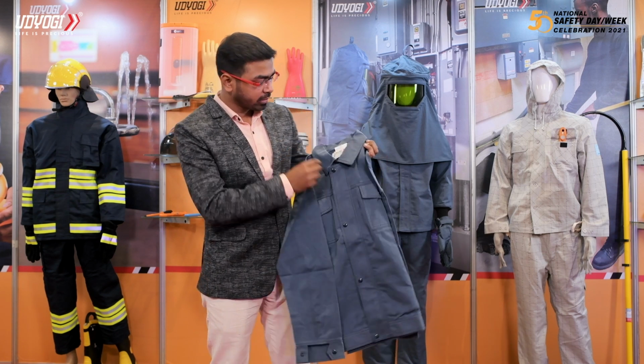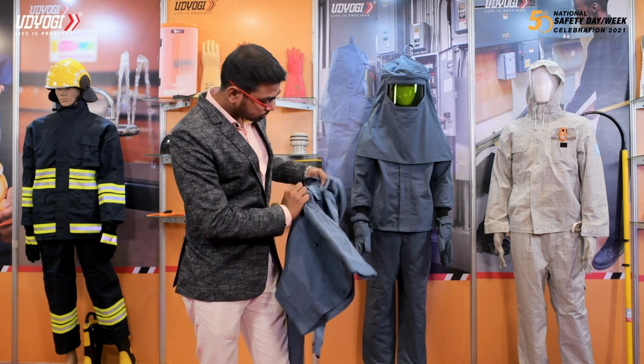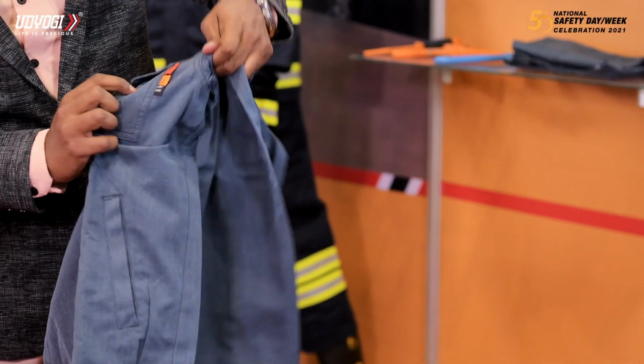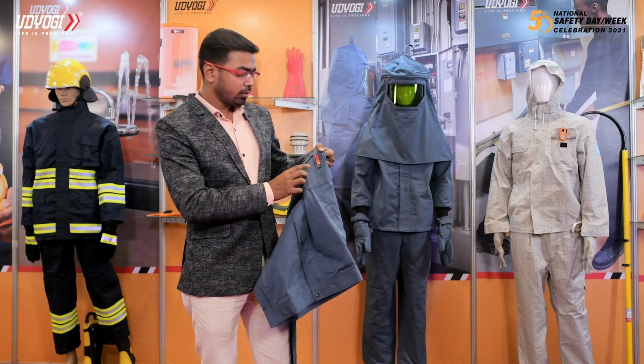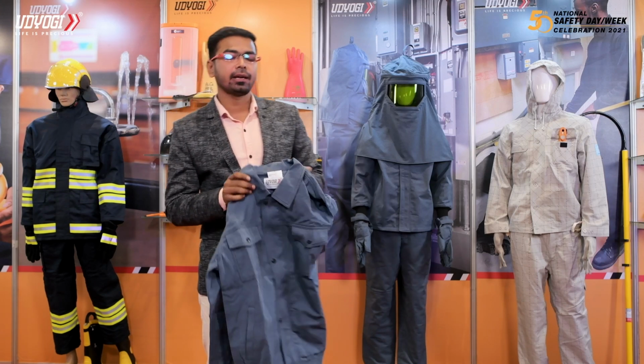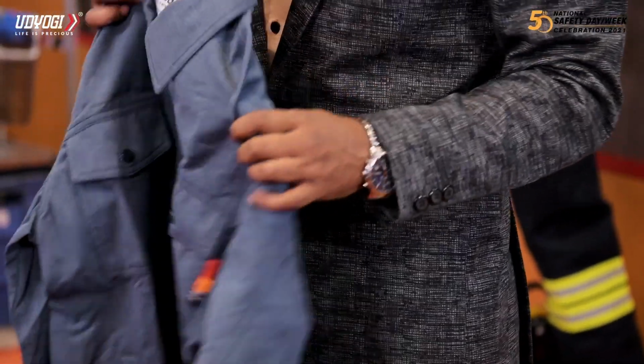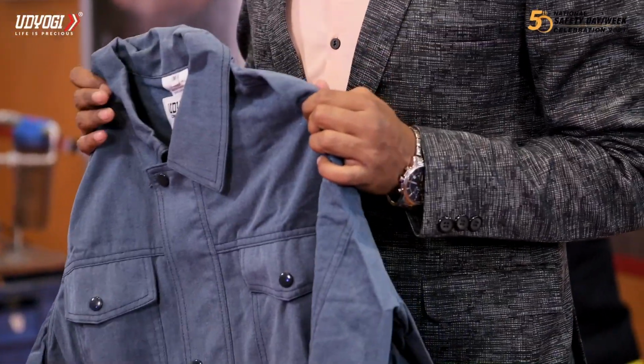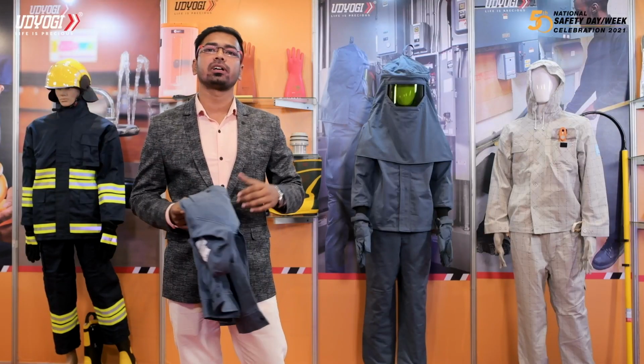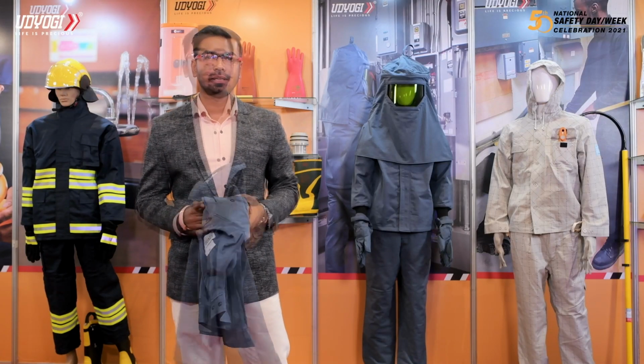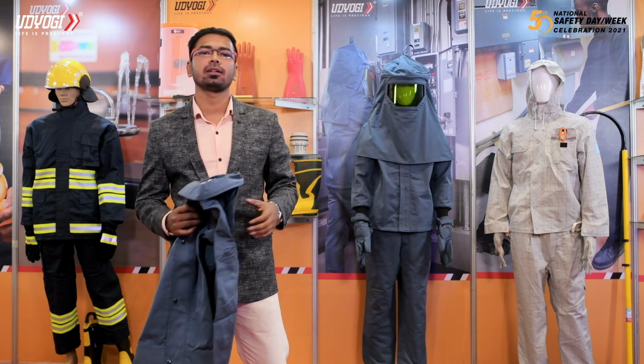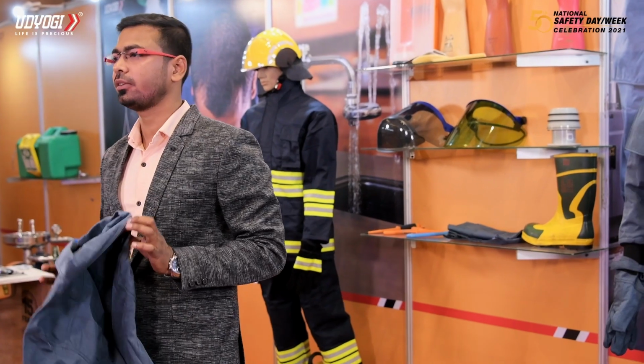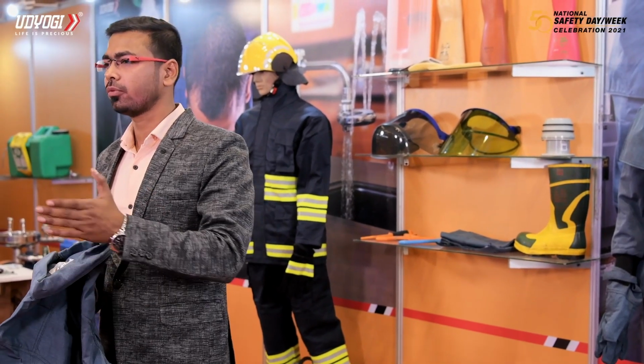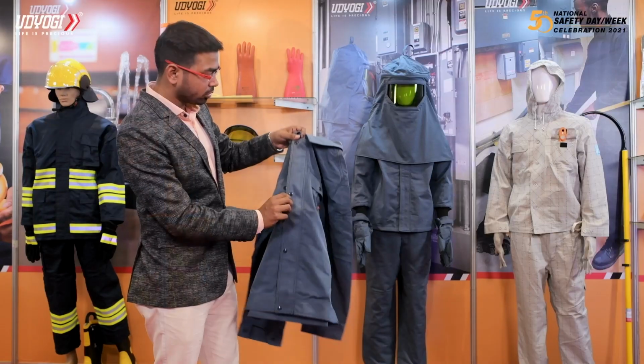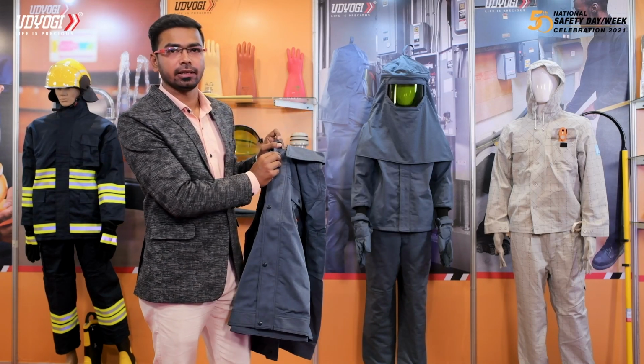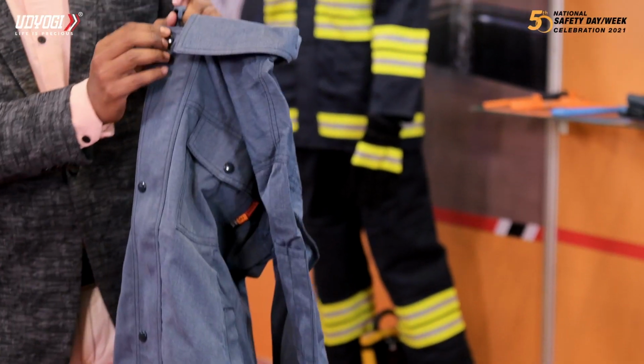If you notice properly, you will find that there is a tag with the marking of HRC2. So what is the meaning of this? The meaning is Hazard Risk Category, which is defined by NFPA 70E. Have you ever thought whether your garment is certified or only the fabric is certified? In our case, both the garment and fabric are certified as per ASTM F1959 and ASTM F2621. The materials we use in our garments, like the snap button, are FR or flame retardant.